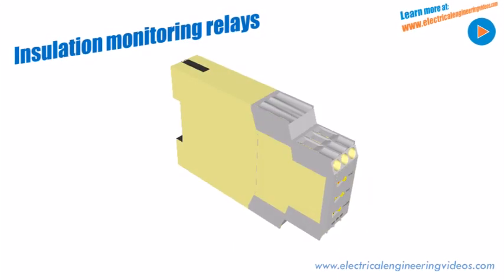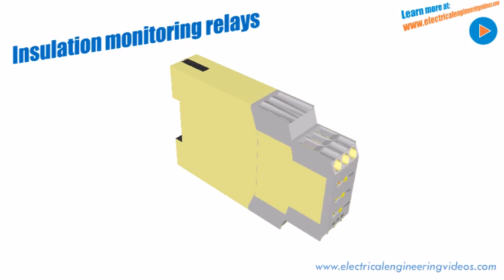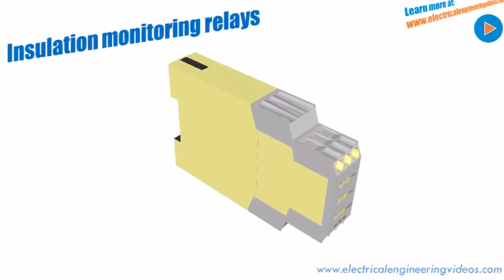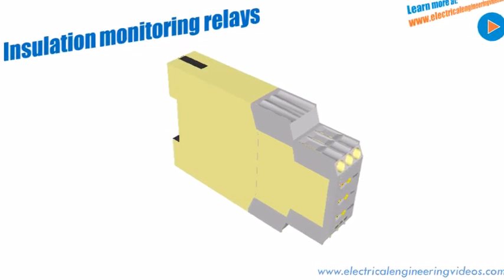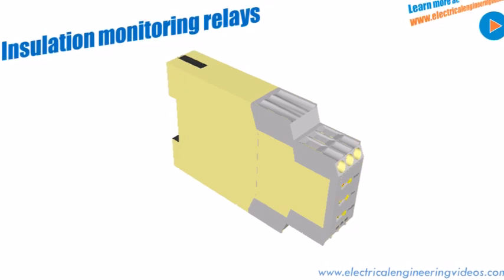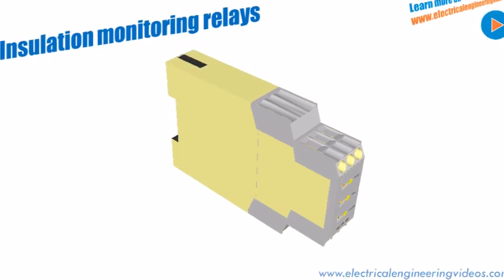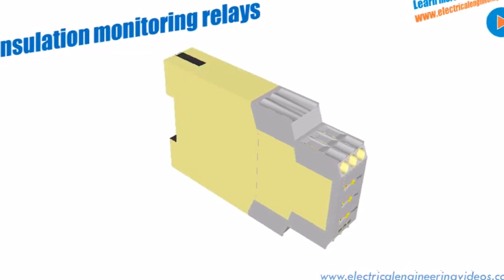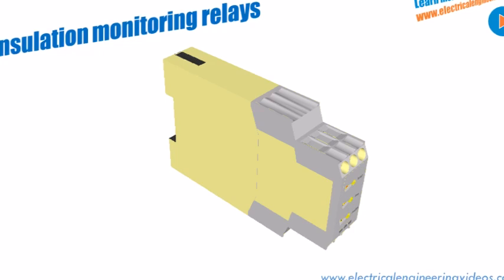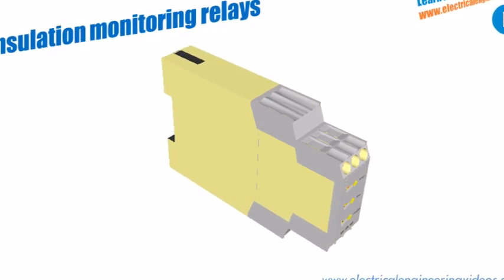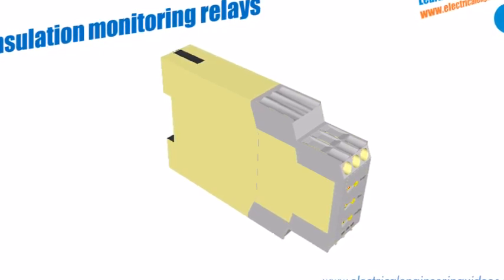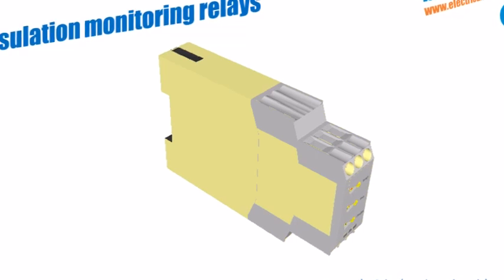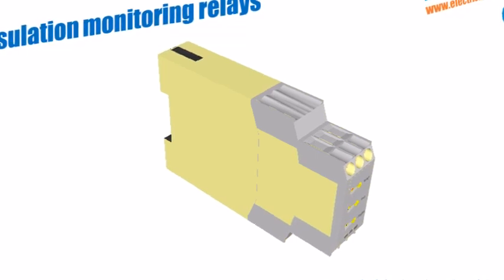The insulation monitoring relay detects insulation faults and trips the circuit if the value falls below a preset value. In such relays, a superimposed DC measuring signal is used for measurement. The insulation resistance is calculated from the superimposed DC voltage and the resultant current.